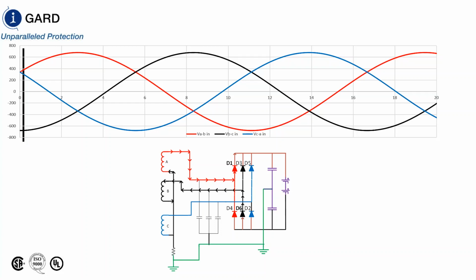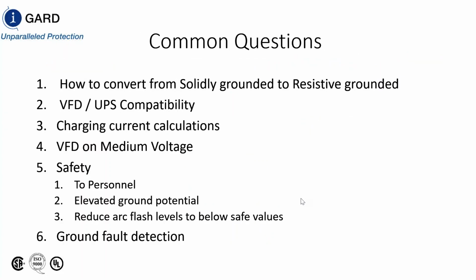We do have relays that will protect you against that as well, and automatically shut off the feeder that is of lower priority. I know you didn't put that one in, but it was under some consideration as well. Yes, sir. So that's like Sergio said, that's another level of design that we weren't able to fund, that we wanted to put in those relays for that, and then do some coordination tripping to eliminate that as well.